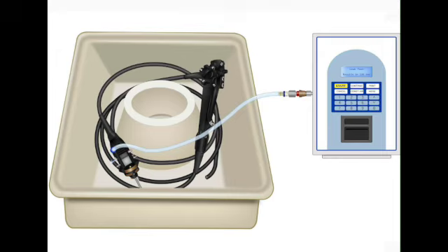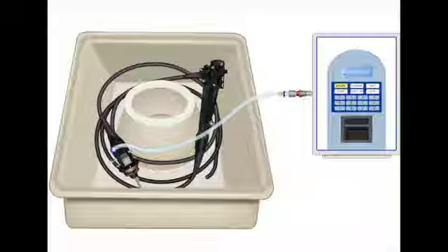But the stakes go way up if it fails a second time. They do. A second fail means the scope itself is breached. And now you're in a whole different protocol. An emergency protocol, almost. You could call it that. At this point, you switch the leak tester to constant air. Okay, so it's just pushing air through continuously. Right. And you are now looking very, very closely at the scope, especially the distal tip, the very end of it. What are you looking for? This is the single most important observation you will make. It determines whether or not that scope can ever be submerged in water again before it's repaired.